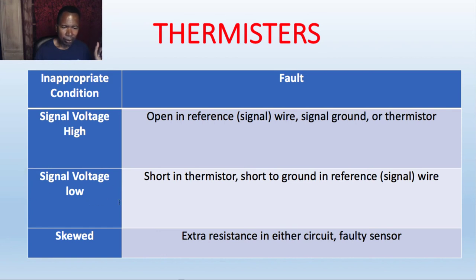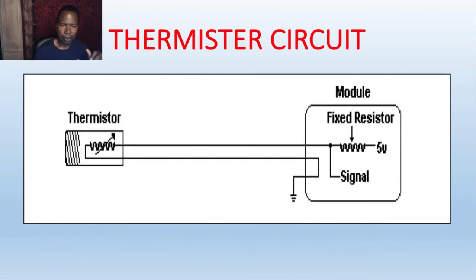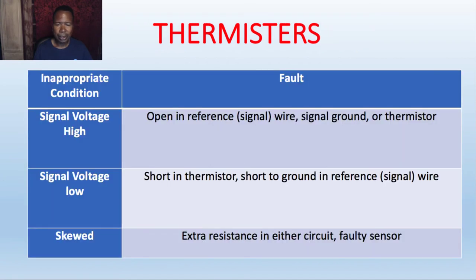Signal voltage low: short in the thermistor, short to ground in the reference signal wire. So it says signal voltage low. I don't think I mentioned this last time, but this 5 volt power supply wire on this line is also the signal wire for a 2-wire sensor. So what this is saying here is that signal wire is shorted.